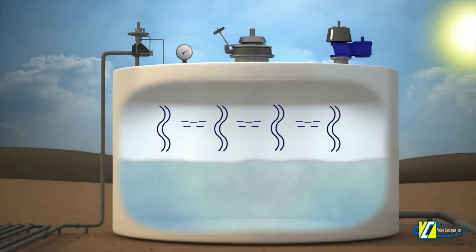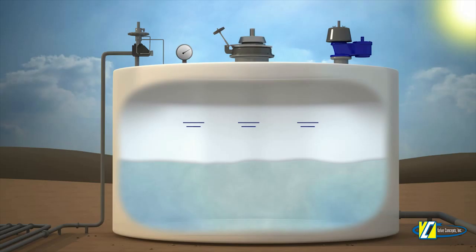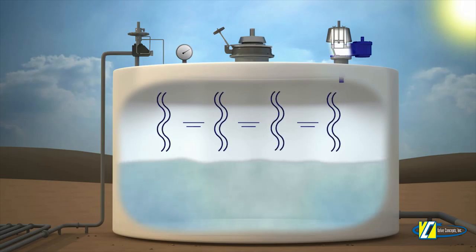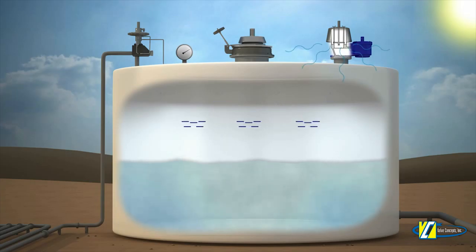As the sun rises in the morning, the vapor space inside the storage tank will naturally begin to heat up, causing the pressure inside the tank to build. As this pressure begins to build, the pressure side of the PV vent will begin to open, alleviating the tank pressure to a safe level.